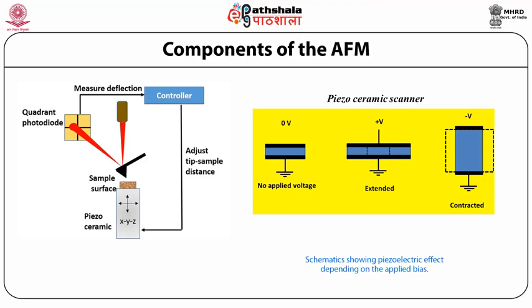The scanner is constructed by the independent combination of piezoelectrodes for X, Y and Z position coordinates into a single tube or flexure scanner. The scanner formed can manipulate samples and probes in the 3 dimensions with highly accurate precision.